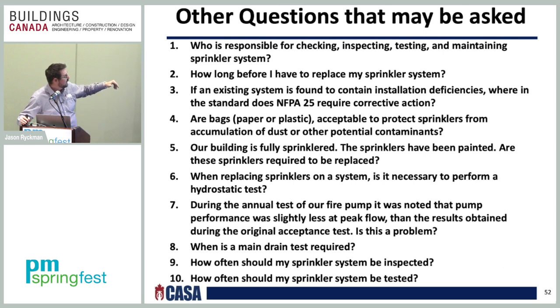Some other things. When replacing sprinklers on a system, is it necessary to perform a hydrostatic test? The answer is yes. If you have to replace sprinklers on your system and there are more than 20 sprinklers, you have to do a hydrostatic test. That would actually be in the installation standard, since you're taking out the sprinkler head and reinstalling it. Then it goes into the installation standard, which stipulates that if more than 20 sprinkler heads are being replaced, you have to hydrostatic test it. Also, with that in mind, if you do replace the sprinkler, it has to be a new sprinkler. You can't reuse sprinklers. Because of time, I'm limited.